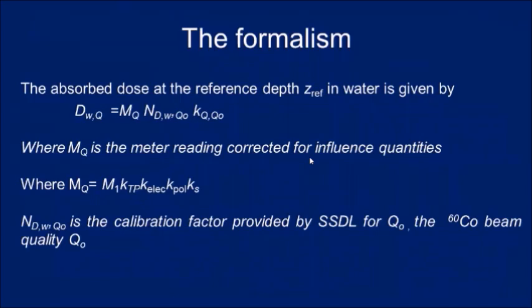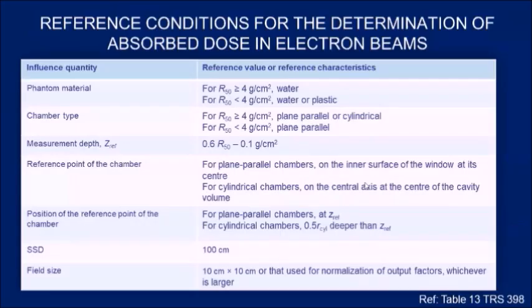The formalism is very similar to what we use for photon beams: dose to water for a particular energy equals the meter reading corrected for influence quantities, multiplied by NDW,Q0 and KQ,Q0, which converts from the reference energy to the energy in question. MQ is obtained by multiplying the meter reading by pressure-temperature correction, polarity correction, recombination correction factor, and electrometer calibration factor if calibrated separately. NDW is the calibration factor from the SSDL or PSDL for reference energy Q0, which is mostly cobalt-60.